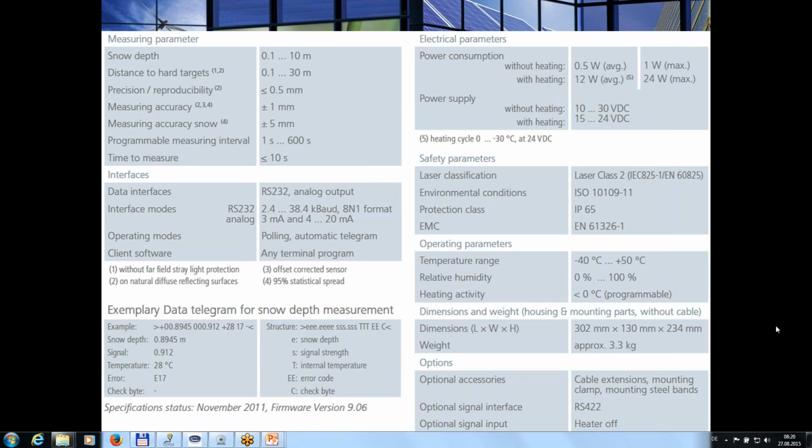Why? The reason is that in the past, before 2012, we measured more or less only the snow depth, and the sensors were only calibrated for snow depth. And for snow depth, in principle, the total measuring range is the same as for hard, up to 30 meters. Due to our stray light reduction, we have a limited distance of 10 to 15 meters.